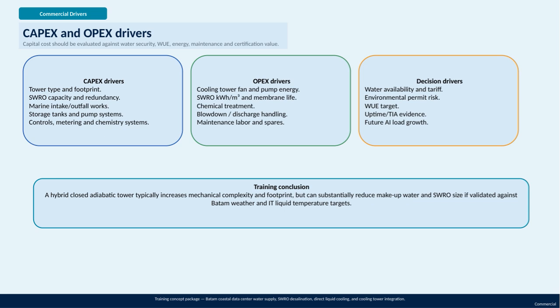Decision-making also depends heavily on external factors like water availability and tariffs, environmental permitting risks, the water use efficiency targets, evidence for uptime as per TIA standards, and anticipated future AI load growth. In conclusion, using a hybrid closed adiabatic cooling tower may add some mechanical complexity and take up more space, but also has potential to significantly reduce both makeup water requirements and SWRO system size. This approach should be carefully validated against Batam's local weather conditions and the IT liquid temperature targets to ensure optimal performance.